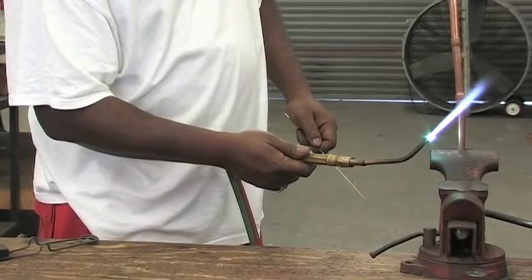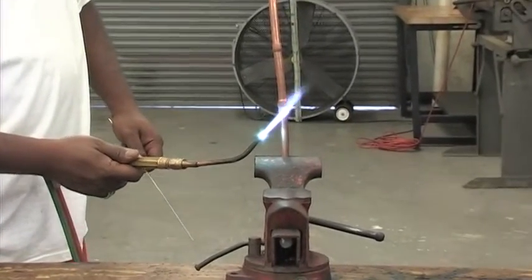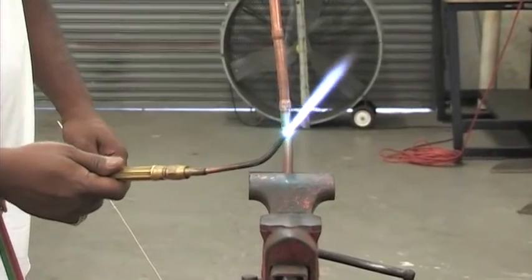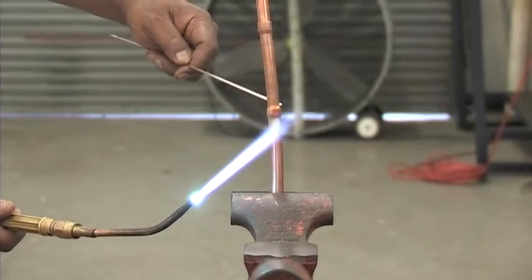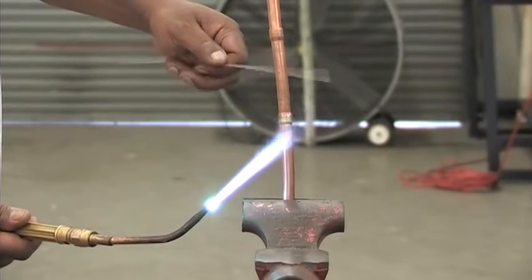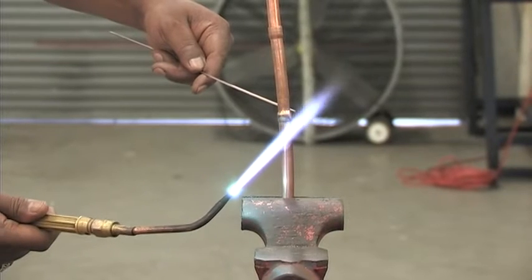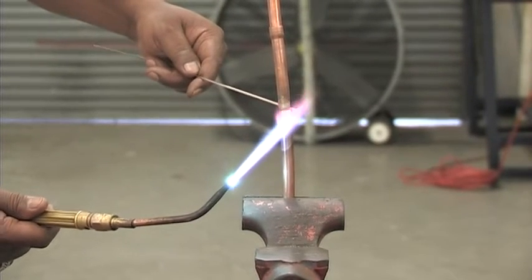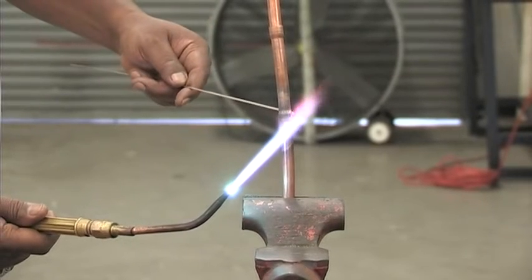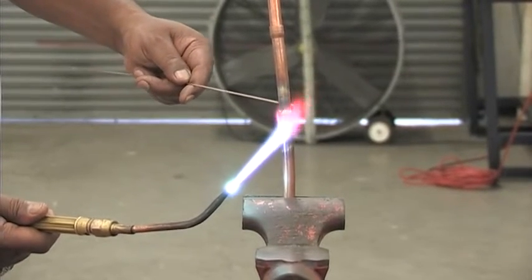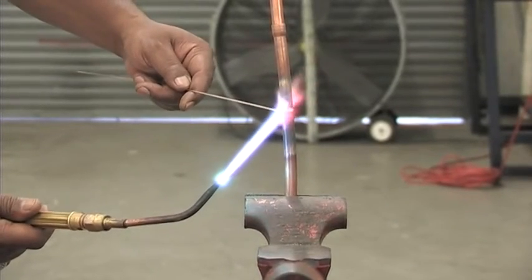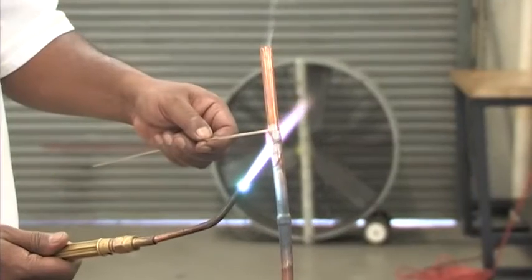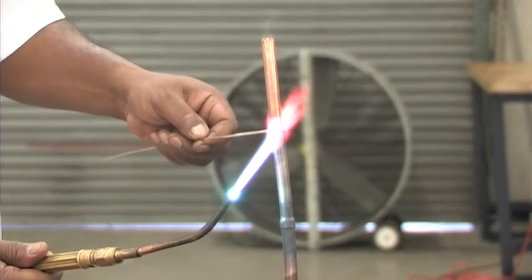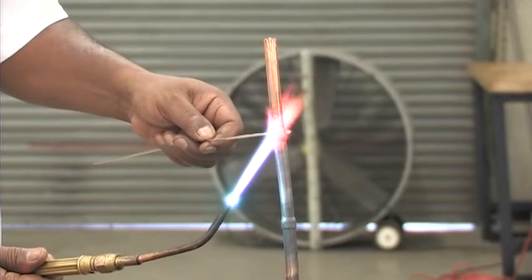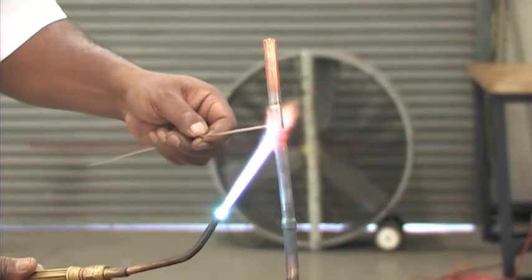Toy now will apply heat to the copper pipe. As he applies the heat, he will apply the brazing stick. The heat of the pipe will melt the stick and seal the joint. Now he'll do the top joint. Soldering and brazing is very important because copper pipes carry the refrigerant, which facilitates the cooling of the equipment.